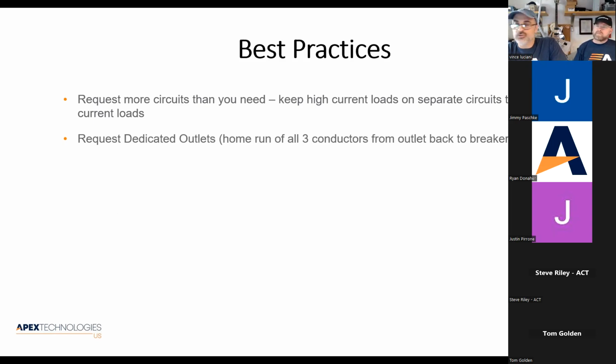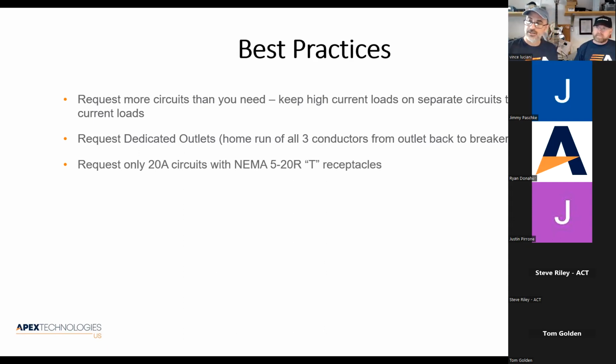Dedicated outlets, we talked about those. The definition of a dedicated outlet: a home run of all three conductors. I've seen a couple of situations where the dealer said, yes, I asked for dedicated outlets. What does that mean exactly? Okay, well, the hot wire was run and dedicated to one outlet, and then the neutral wire, you opened up the outlet and there's two wires on there. It's like, why is there two wires on the neutral? That neutral's going somewhere else. Yeah. It's like, that's not dedicated. Maybe the lighting can. Yeah, man. The ceiling fan. Yeah, who knows? They need to pick up a neutral somewhere. All three conductors, line, neutral, and ground, home run from the outlet back to the breaker panel. We said this before, just go ahead and ask for 20 amps.